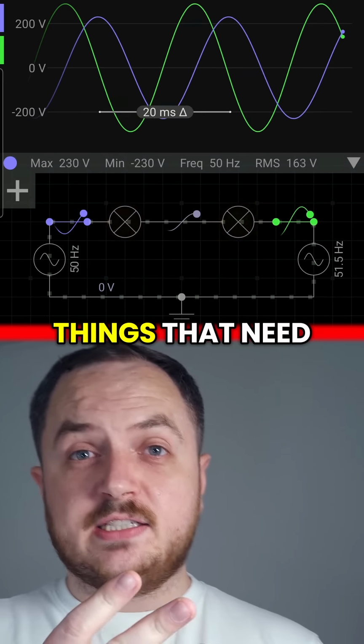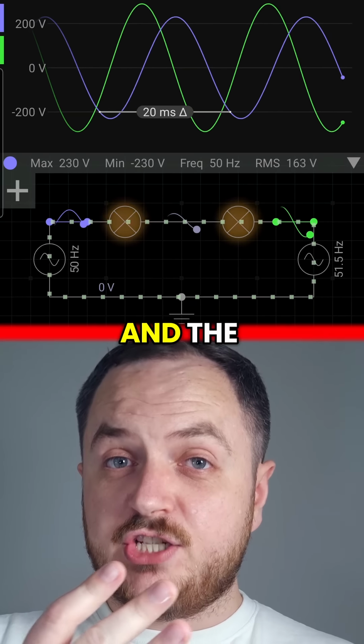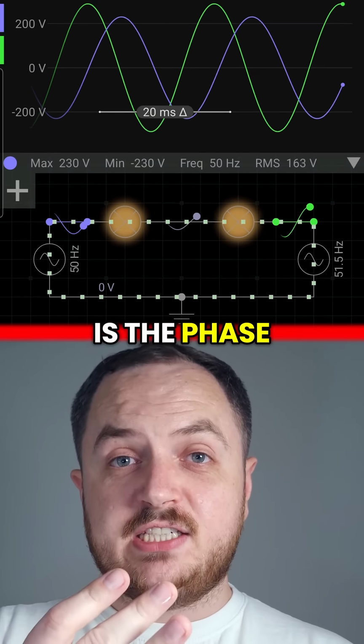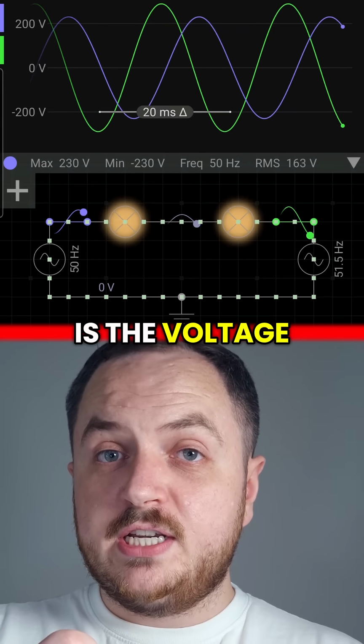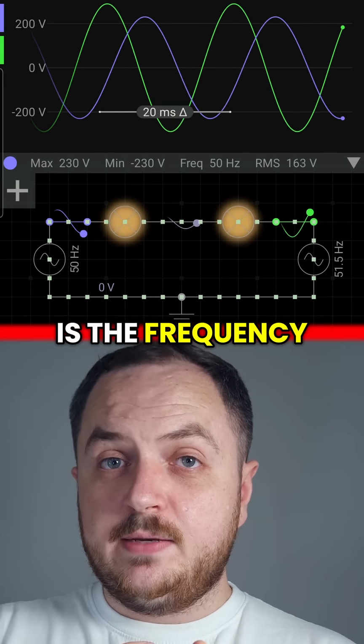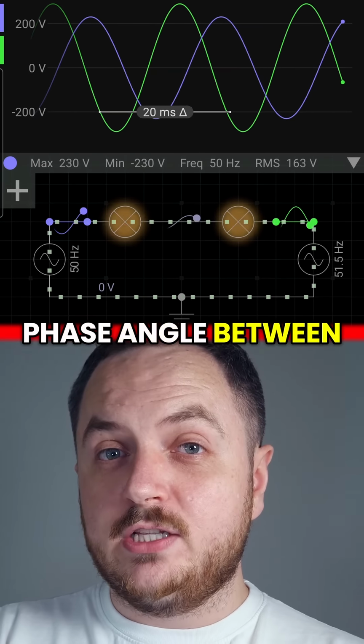There's 4 key things that need to match between the main supply and the generator supply. The first one is the phase sequence. The second one is the voltage. The third one is the frequency. And the fourth one is the phase angle between the two supplies.